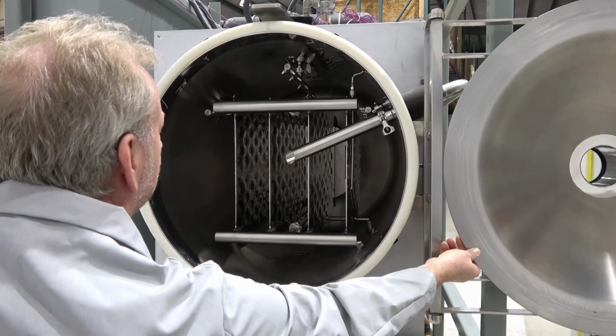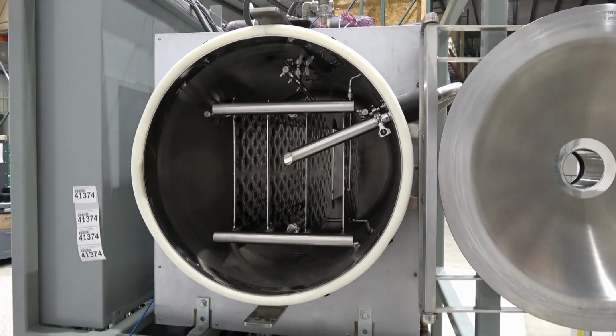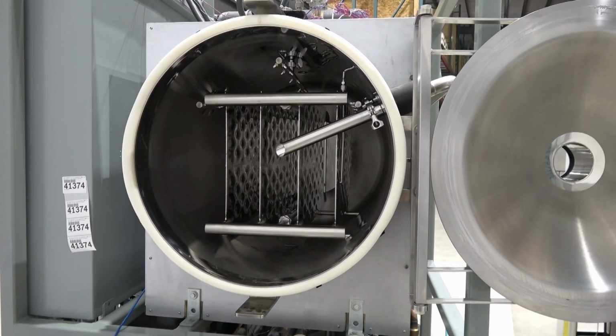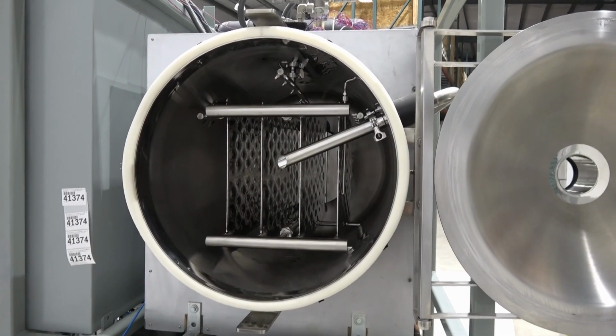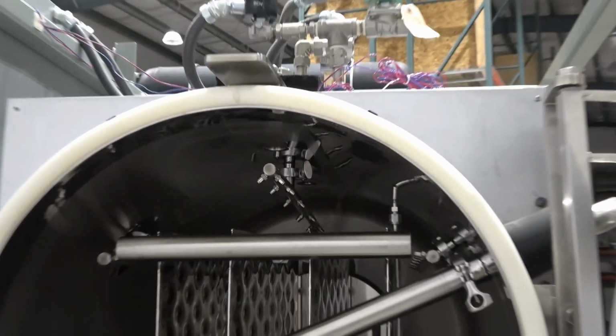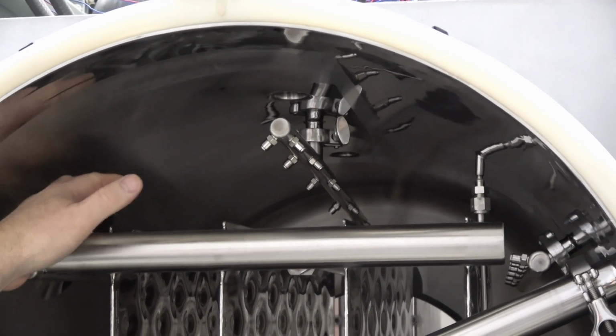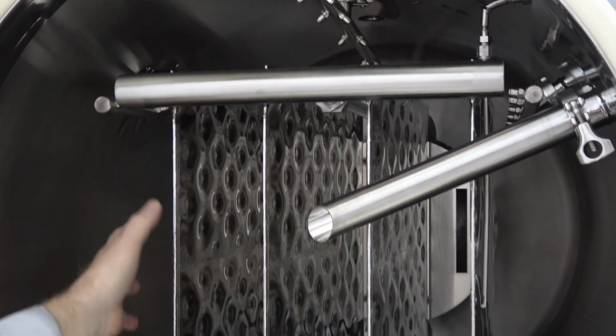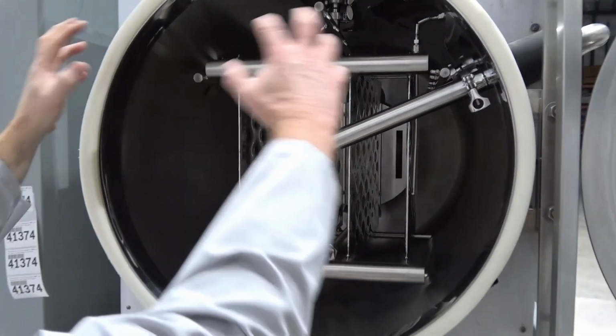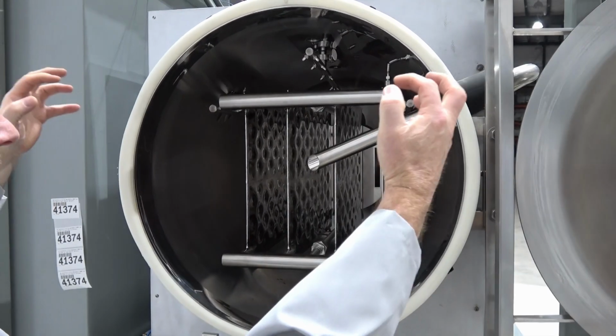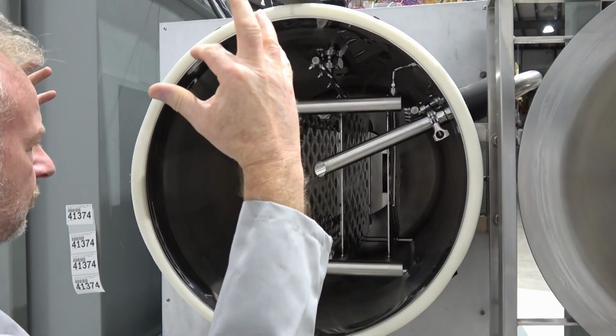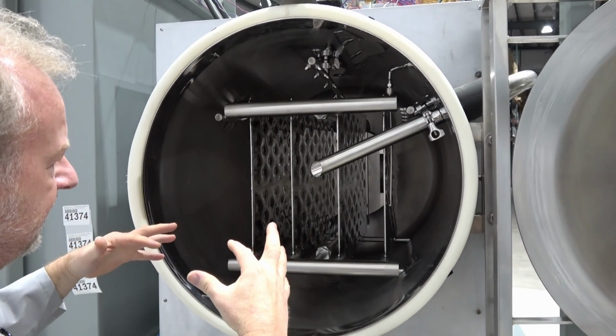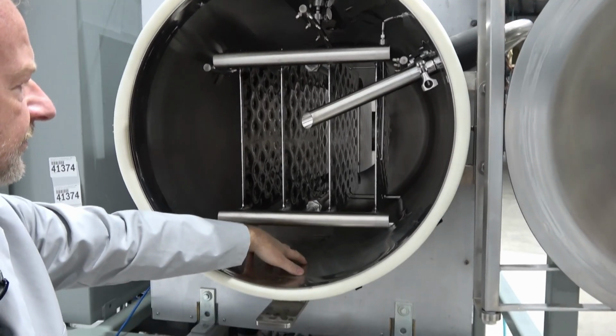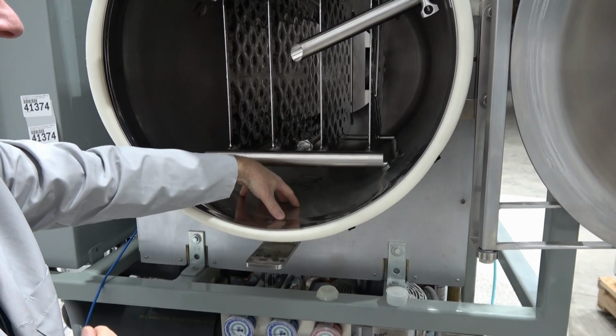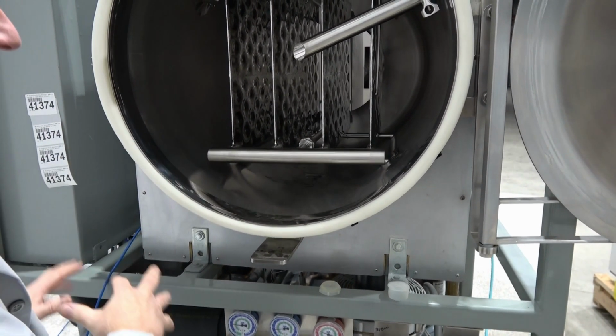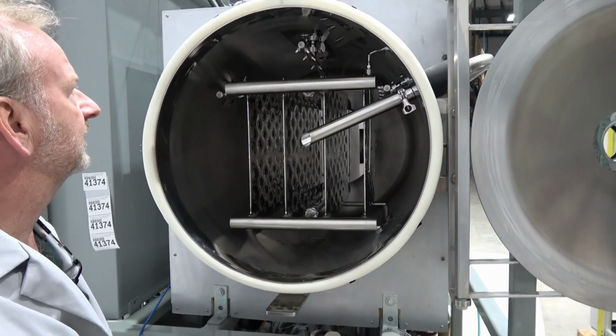This does have the hot water defrost system where you pipe in hot water and it sprays everything down with these spray nozzle jets. So you have four condenser areas where you'll build up ice, and then you bring in hot water to do a really quick defrost, and then of course the drain automatically opens up in the defrost mode and drains everything accordingly.